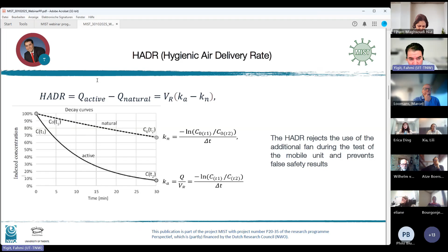What did we do next to prove it in practice? We just took several professional and semi-professional devices. We took their own published papers, like you see on the right, a screenshot from the first device, which was published by Professor Kähler in Munich in Germany, the reduction dilution curve from device A, which claimed to have 1200 cubic meters in a classroom of 200 cubic meters, which means an air change of 6. An air change of 6 means that it should dilute the contamination within 23 minutes. You see the green spot on 0.4. But in practice, it did it in 0.6.